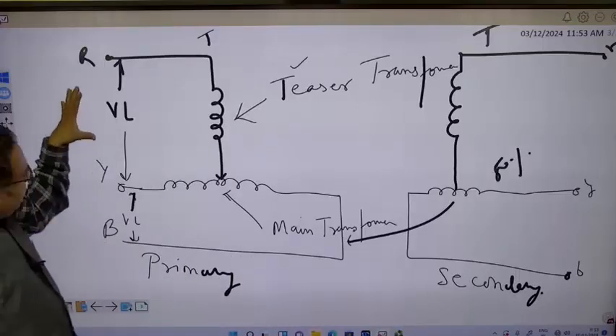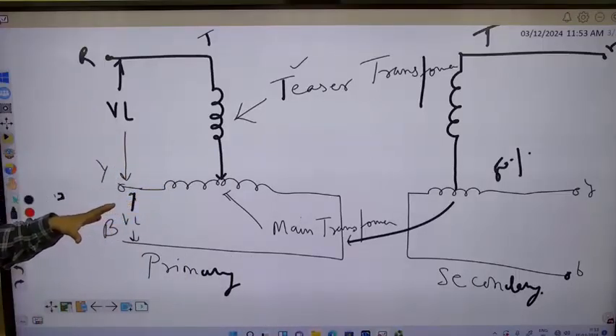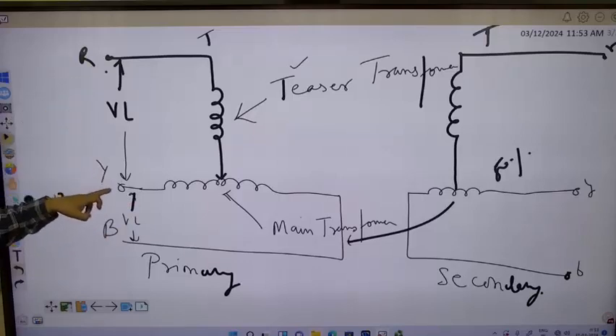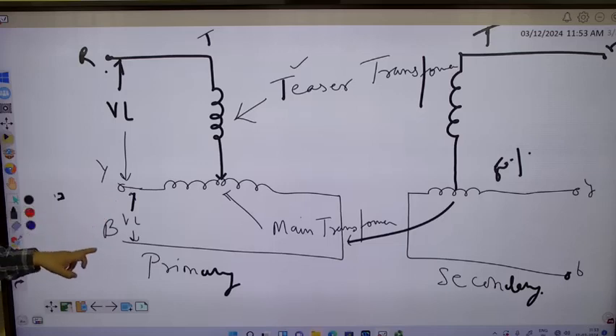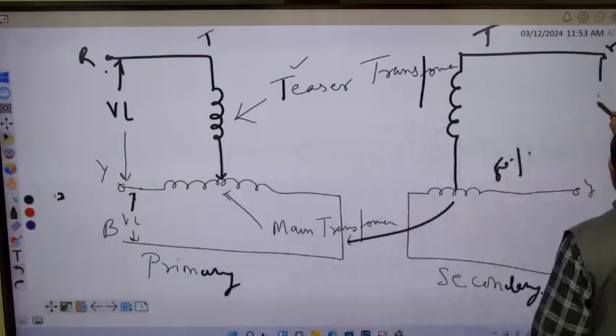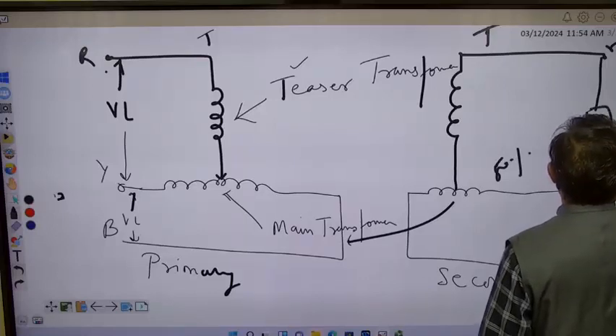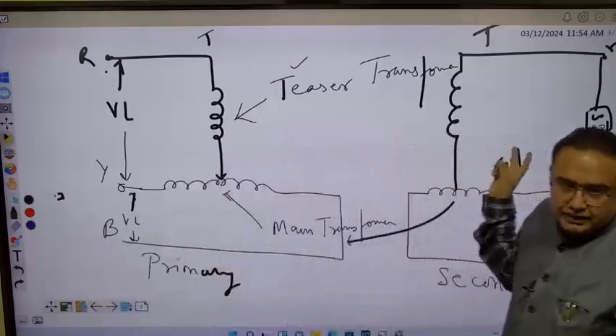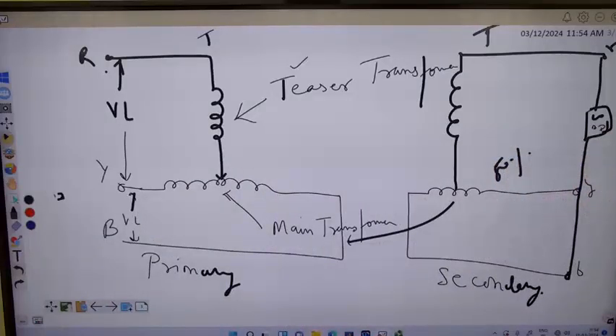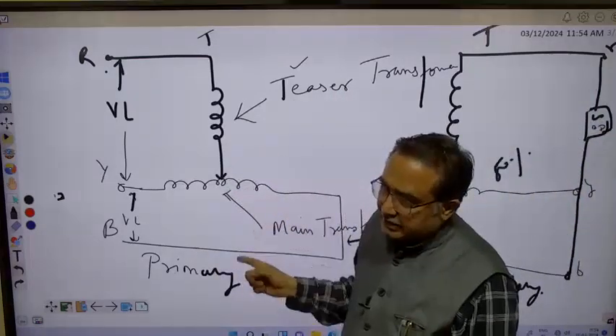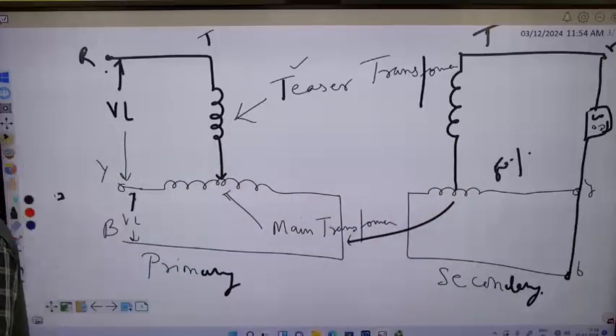We have only two transformers, but we are giving R to this terminal, Y to this terminal, and B to this terminal. Similarly here also you connect the three-phase load. So two transformers, meaning two windings, are being used to provide the load which is of three-phase nature. This configuration is known as Scott-T connection.